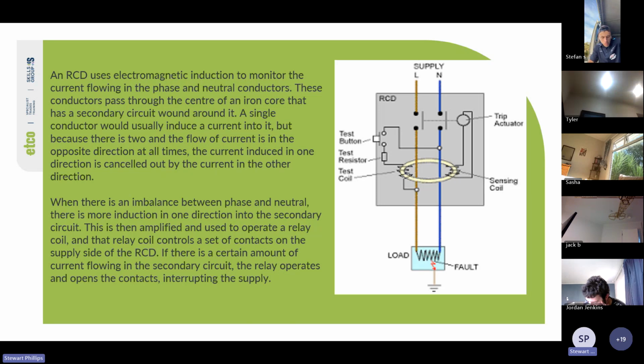And if you notice, there is a test coil there. So when the test button is pushed, a resistor connected to the neutral, and then connected to the phase and back to the neutral, but on opposite sides of the coil, is engaged. This means that it induces a slight inductive field into the sensing coil, which then activates the trip actuator. So that's all the test button does, it checks that the RCD is working. It doesn't test that it's actually tripping at the correct current. It's just a push button test.